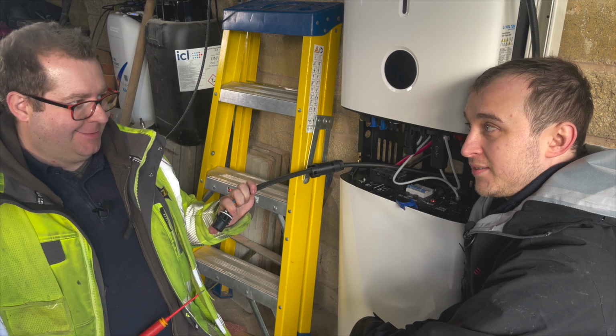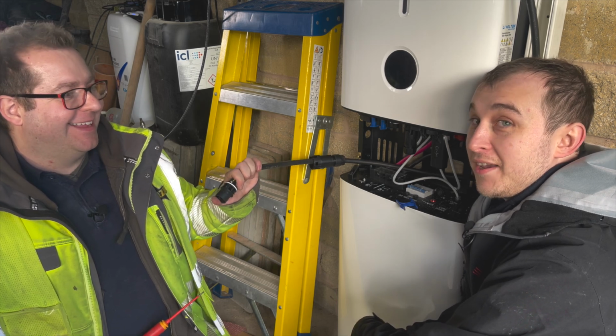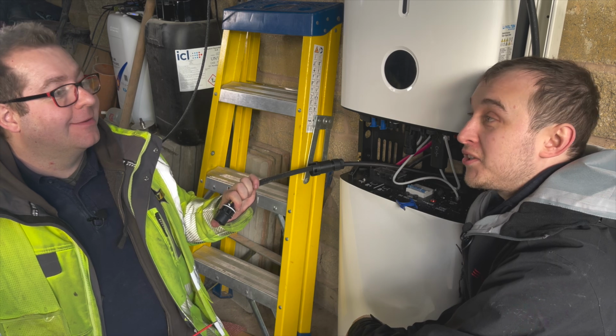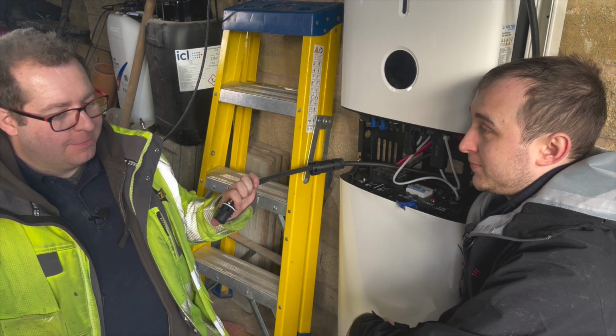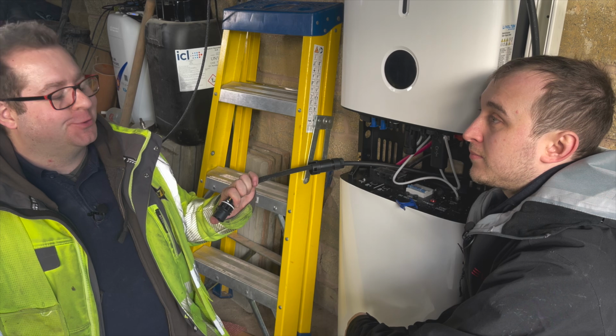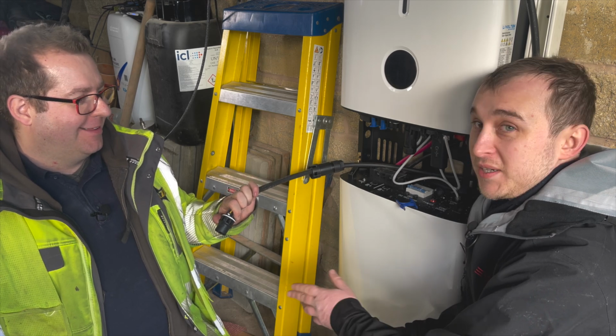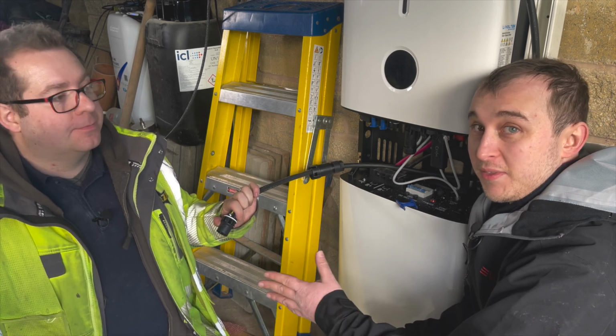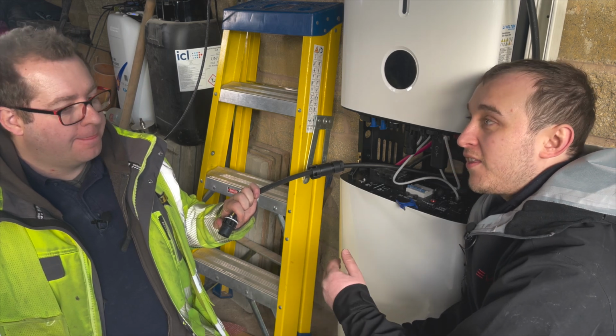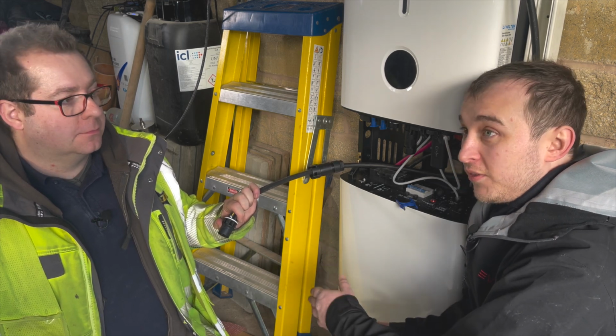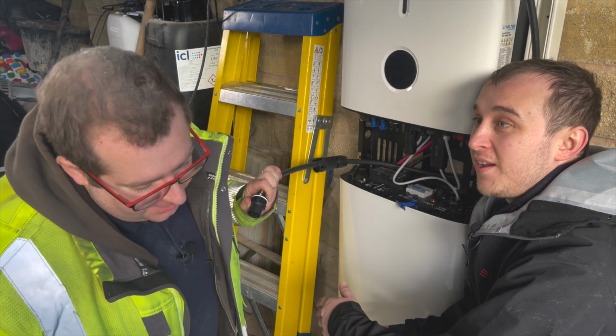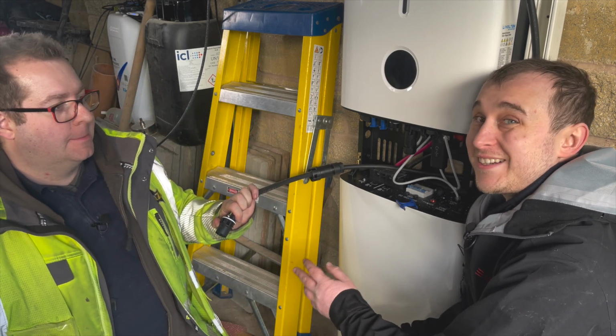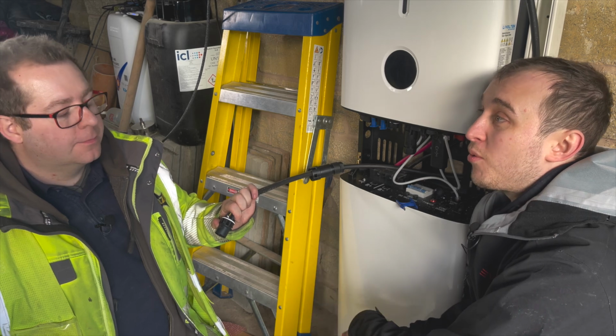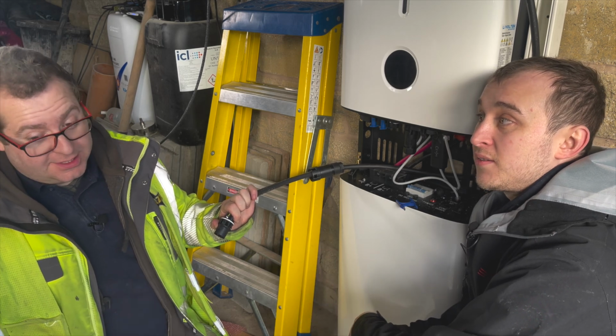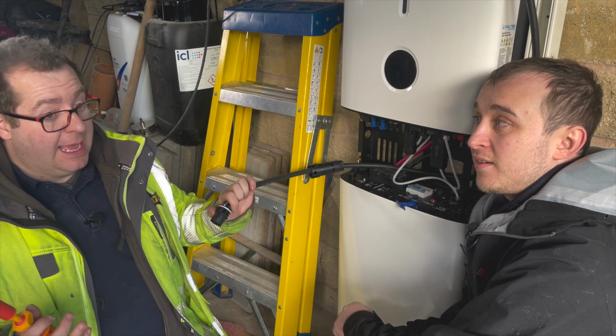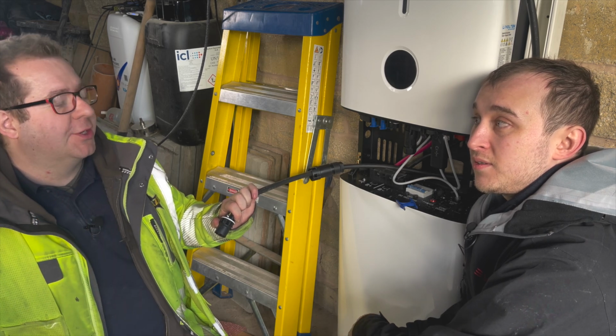Technically, yes. But if you were a naughty boy, you could cause all sorts of potential havoc. Especially for people working on the grid, because the genuine reason for a power cut might be they are working on the electricity lines - they've turned the power off so they can work on them. If you then plug this into the battery, you could actually harm those people, because the output is still 240 volts and 5 kilowatts, which could easily kill somebody.